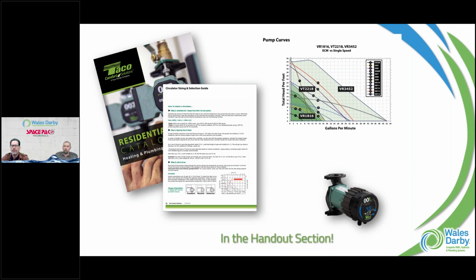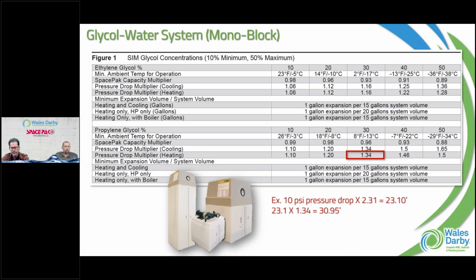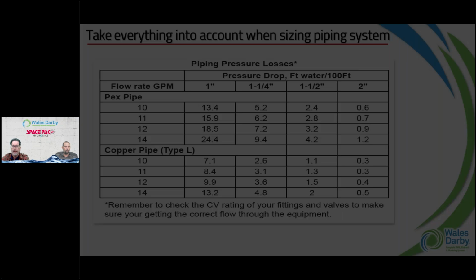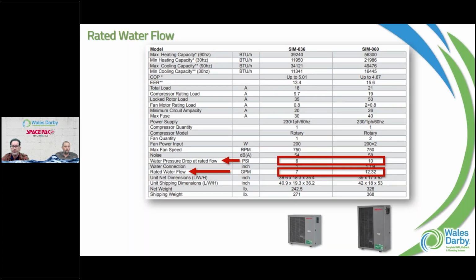Quick question: what is the temperature we will see at minimum heating capacity? I think the temperature is what you set it for. And if our emitters are sized for something less than 120, that's our threshold. I don't know if we're going to get much more if it changes because it's warmer out. We are struggling with refrigerant-based compression turning that into heat energy. So 120 would be our top, and you can lower that if you choose to go to a lower temp gradient application or whatever you choose.